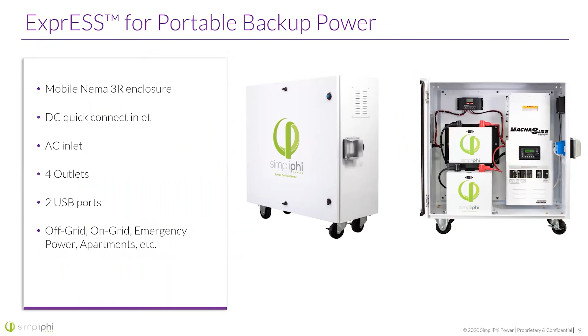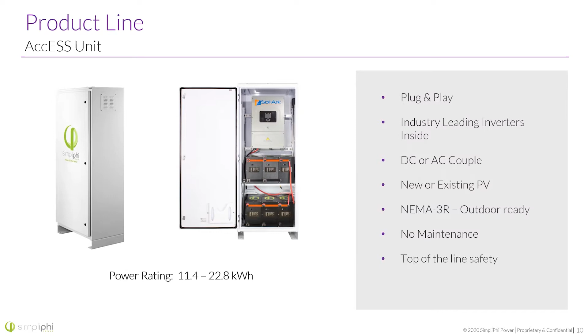On the other hand is our Access unit. This is designed to be hardwired to a panel, whether it's a critical loads panel, or maybe you're looking to utilize it for an off-grid system or something like that. It's battery, inverter, charger, all built into one. Comes in 2 different options, the Sol-Ark or the Schneider, depending on which inverter is being used inside the unit. It can be DC or AC coupled. It is NEMA 3R, so it's outdoor rated. Great for existing PV arrays if you just want to add a battery in. And again, it's pre-programmed and pre-wired for the most part, so it's a little bit easier on installation.